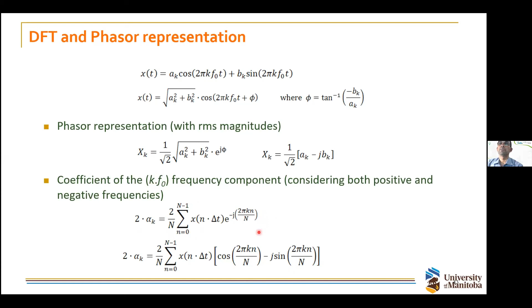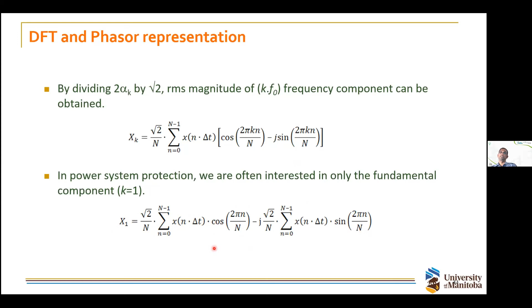So basically, in power systems, mostly we are looking at the fundamental component, because depending on the number of samples that you consider for one cycle, you can get multiple frequency components, that is, the fundamental plus its harmonics, right? The number of harmonics you can calculate depends on your sampling frequency, or the number of samples per cycle. But if you are not interested in all these higher frequency components, which is the case in this situation because we are looking at the fundamental phasor, we only want to compute X1, the fundamental component. Then you can simply compute your real and imaginary parts like this. These x parts are the sample values of your original signal, and then you multiply by the cos and sine functions to get the real and imaginary parts of your phasor.